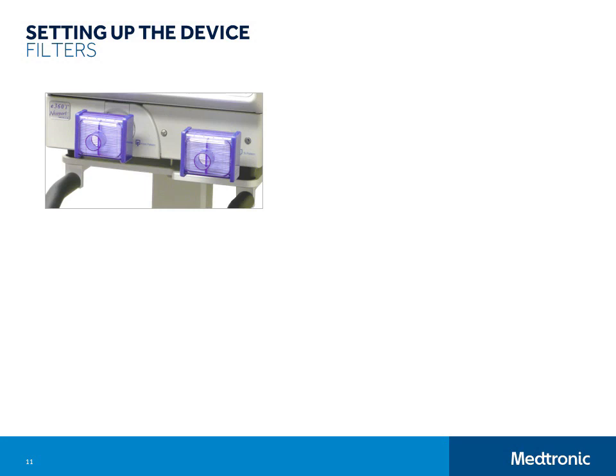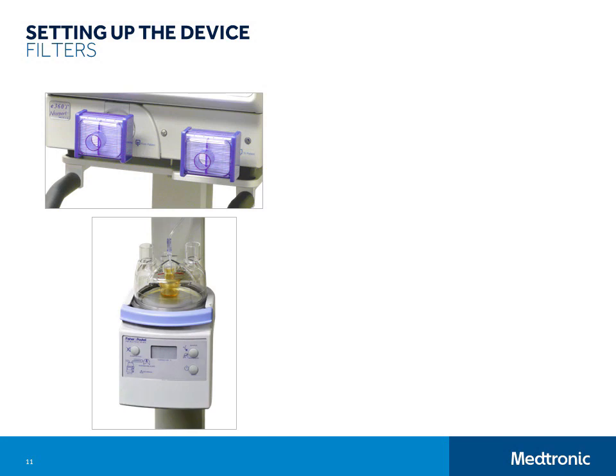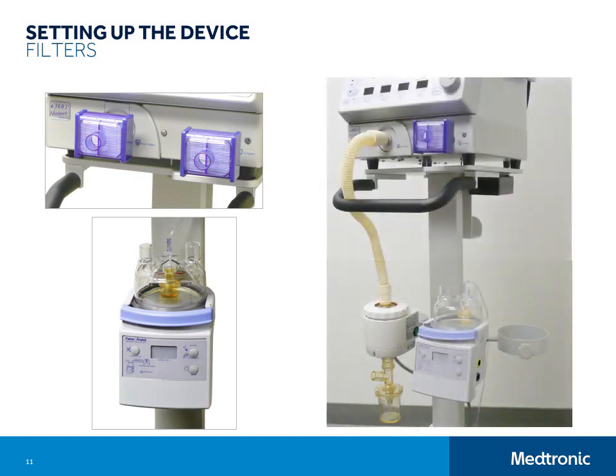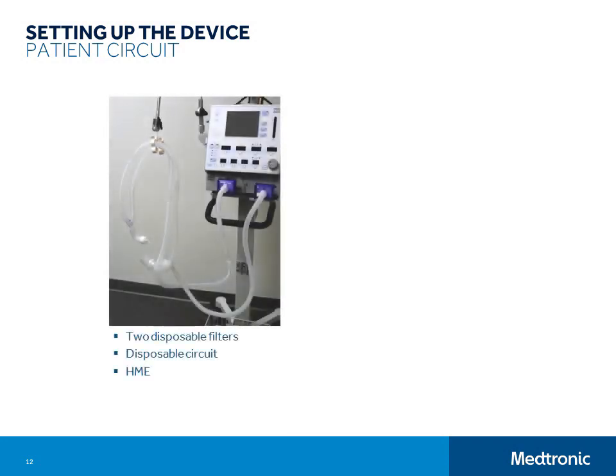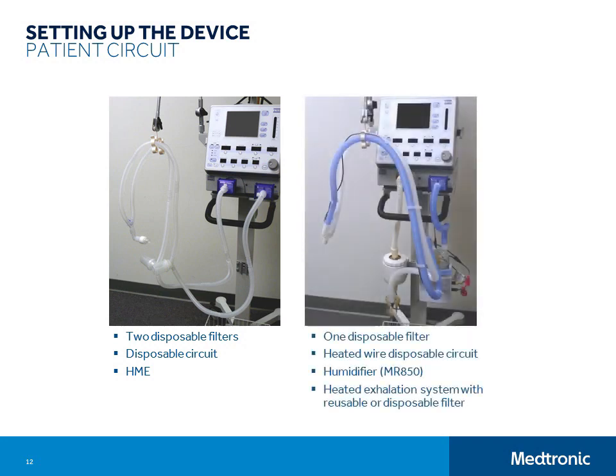If you are using a heated humidifier, attach it directly to the cart or compressor. If you are also using a heated expiratory filter system, you will need to use the T-bar to mount both the humidifier and the filter system. You won't need to attach a filter onto the from-patient port if you are planning to use the heated expiratory filter system. Instead, you will put an expiratory filter inside the heater assembly. Sometimes your setup will be as simple as a 2-limb breathing circuit, inspiratory and expiratory filters, and an HME up at the patient connection. Other times your setup will include a heated humidifier, heated wire circuit, and heated exhalation filter system. Here is one example of a fully assembled system.